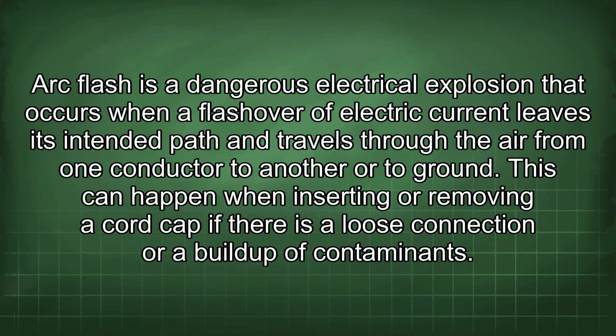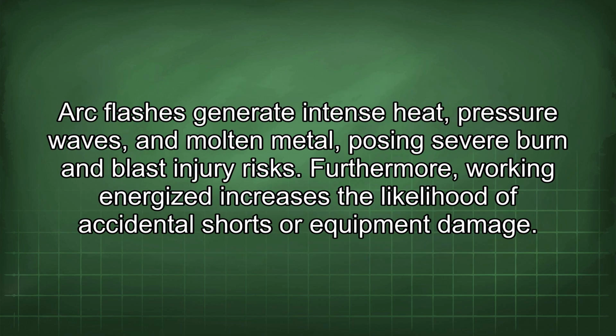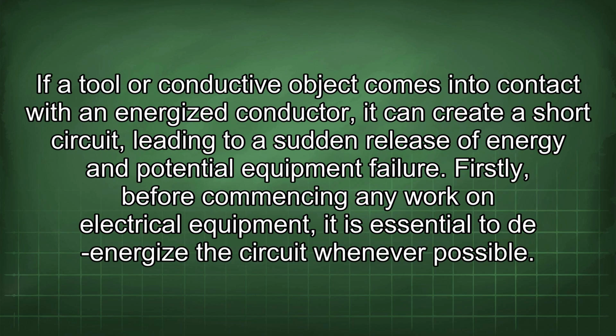This can happen when inserting or removing a cord cap if there is a loose connection or a buildup of contaminants. Arc flashes generate intense heat, pressure waves, and molten metal, posing severe burn and blast injury risks. Furthermore, working energized increases the likelihood of accidental shorts or equipment damage. If a tool or conductive object comes into contact with an energized conductor, it can create a short circuit, leading to a sudden release of energy and potential equipment failure.